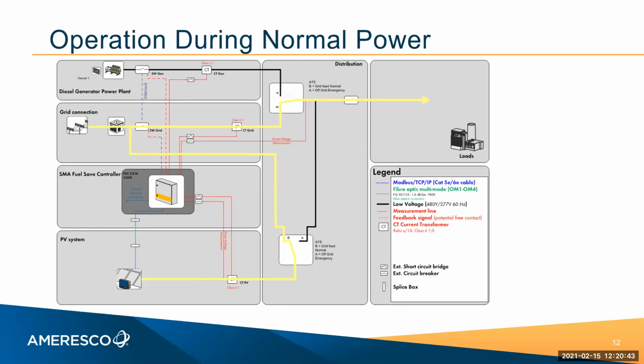It monitors the power output of the PV, which are the CTs on the bottom. It also monitors the power coming from the grid and the power coming from the diesel generator in the top. We don't directly monitor the loads because we are monitoring all of the power supplies. And so if you sum up the power supplies, that would show the loads.